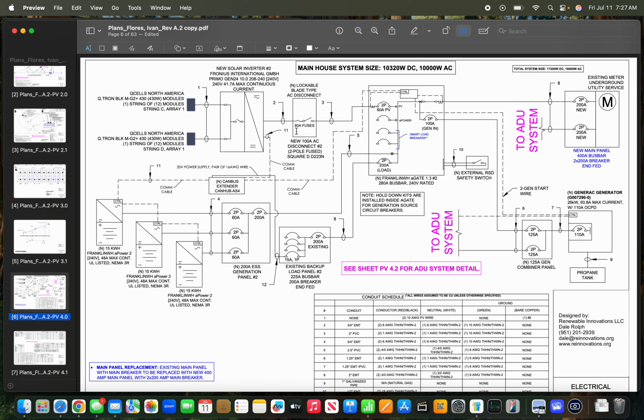Now we did do a fused disconnect, and I specifically put the fused disconnect down by the array and by the inverter because overcurrent protection is really important. And I want to make sure that the equipment stays safe. Given the distance of the run, a fused disconnect near the inverter made the most sense. We're always going to need some form of switchblade disconnect or lockable disconnect for first responders. Even though the inverter has a DC disconnect integrated, a fused disconnect is of great value because it's ensuring that there's protection if there's a surge or just anything on the AC side that malfunctions. It doesn't have to get all the way over to this circuit breaker inside the aGate. It could just blow a fuse and voila, the equipment's protected, the aGate's protected. I just wanted to create some extra protection there.